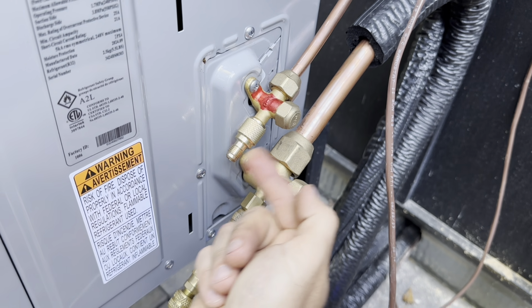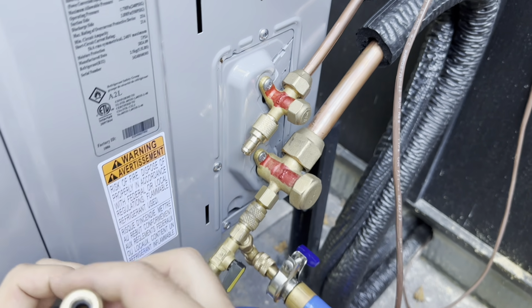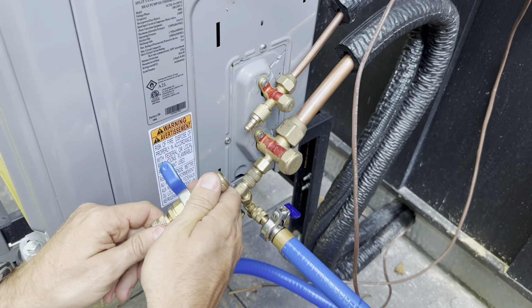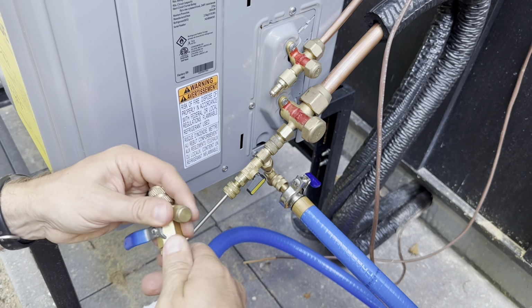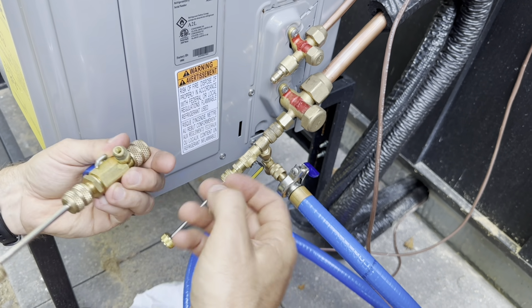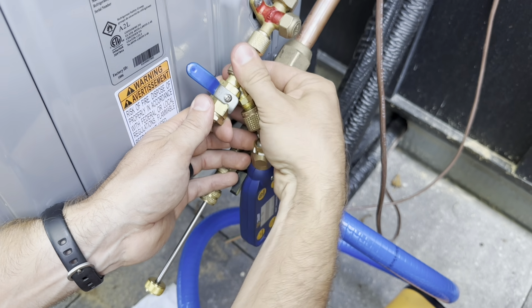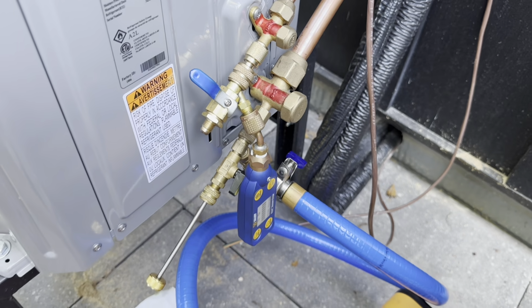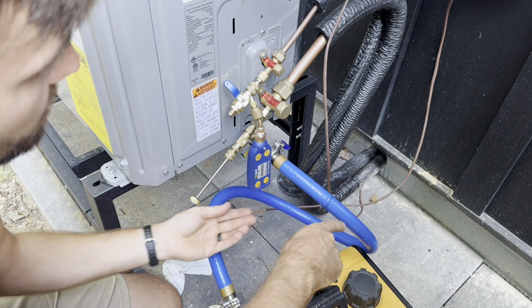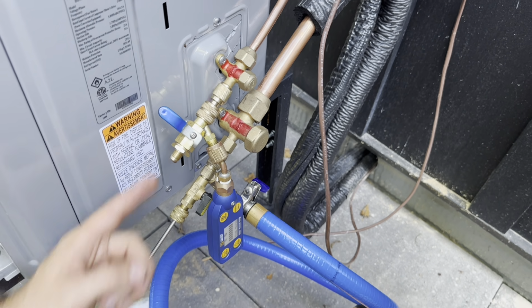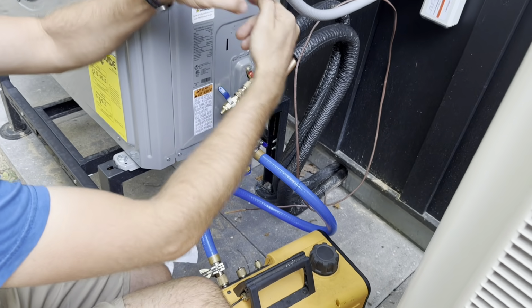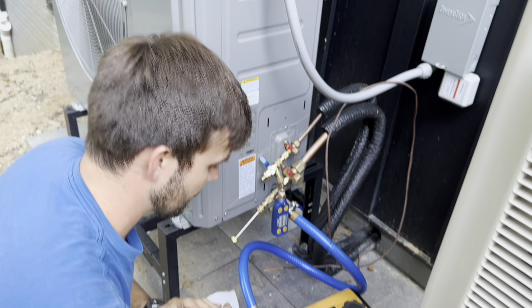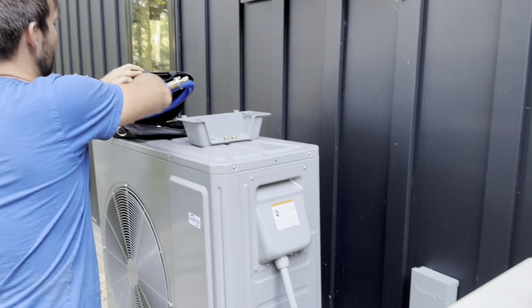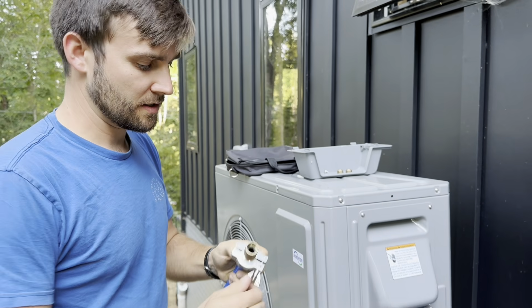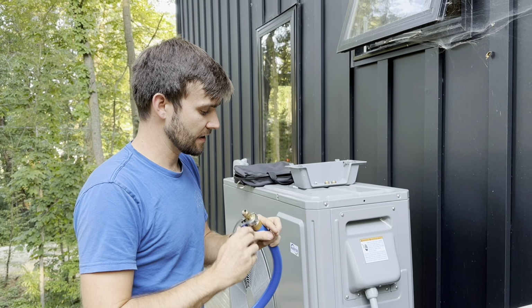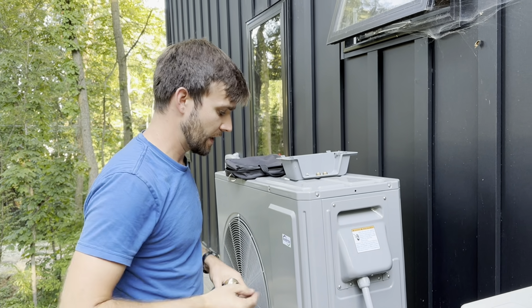This is a 1/4 inch flare fitting. These are like 3/8. So you have to put an adapter on here. And this is a core removal tool, but I'm going to be using it for pulling a vacuum and hooking my micron gauge. He's hooking up multiple to pull a vacuum faster. Yeah, this is my main pull right here on the bigger line. And then I'm going to hook up a second hose here onto the small line. That way I'm pulling vacuum from both sides of the metering device, because it's an EEV, so electronic expansion valve, and it seems to be closed down pretty tight, not letting a whole lot of air be pulled out past it.